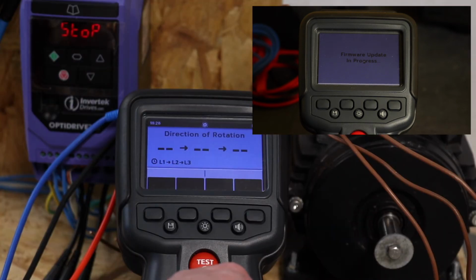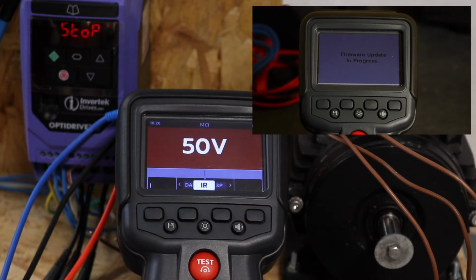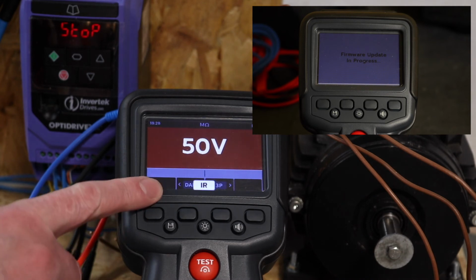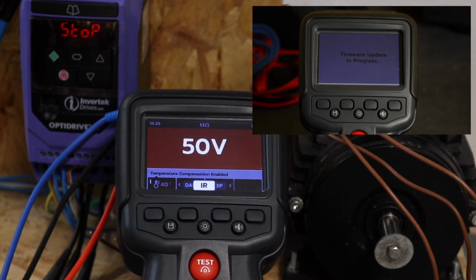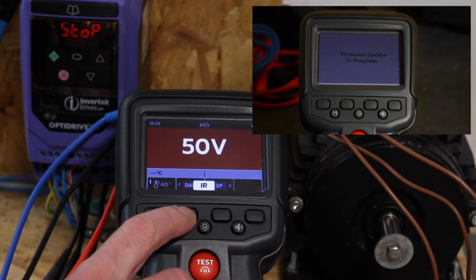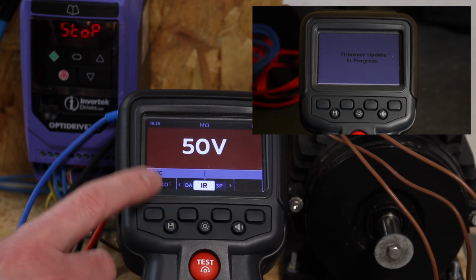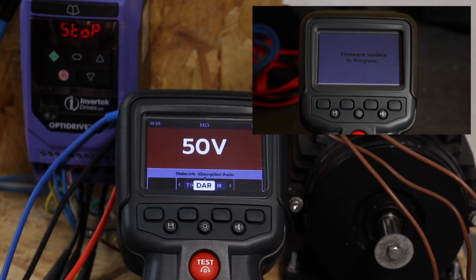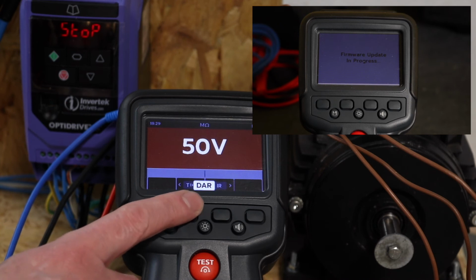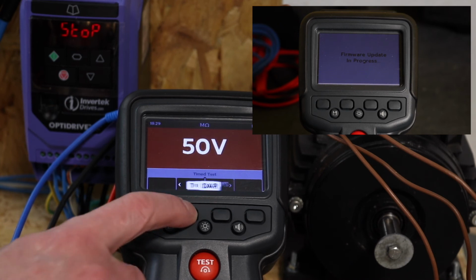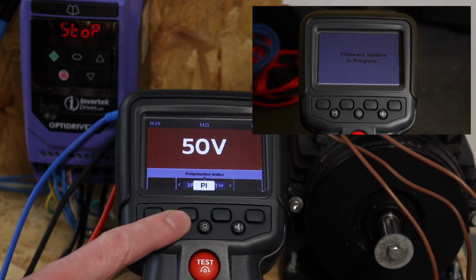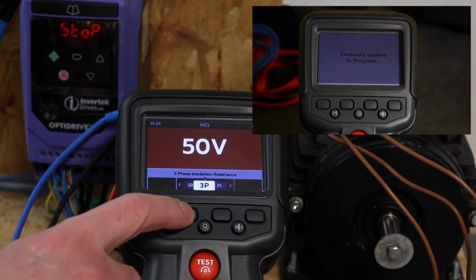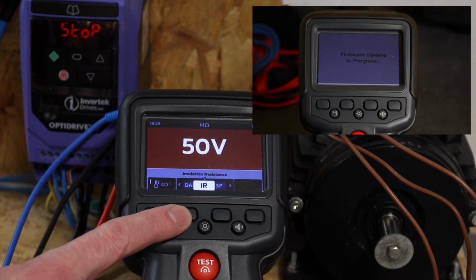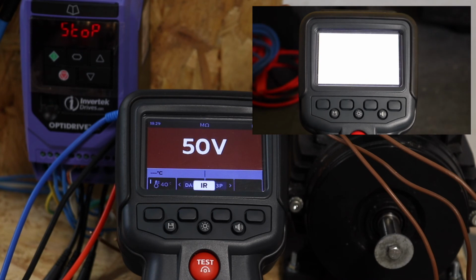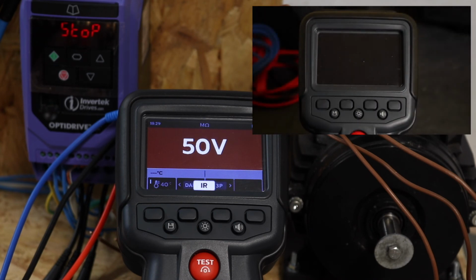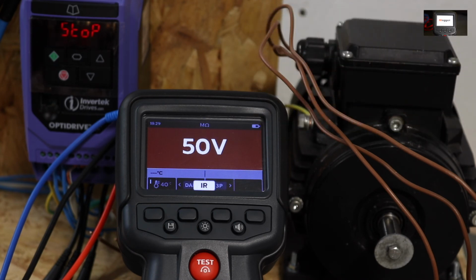So one of the other ones was actual insulation resistance testing. So we have temperature compensation here, which we can turn on. That's not available. It's only available on this spot test. Yeah, it's the same again. So requested it available for DAR and for time testing, but it's just not there, is it? Yeah, doesn't look to include that as well.